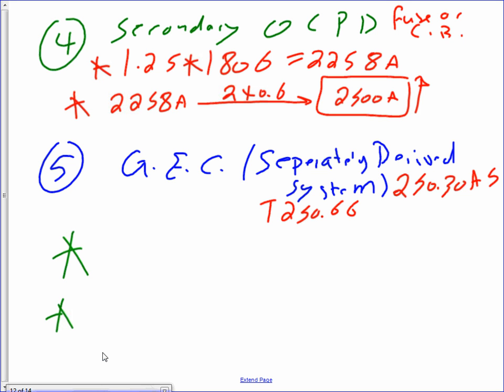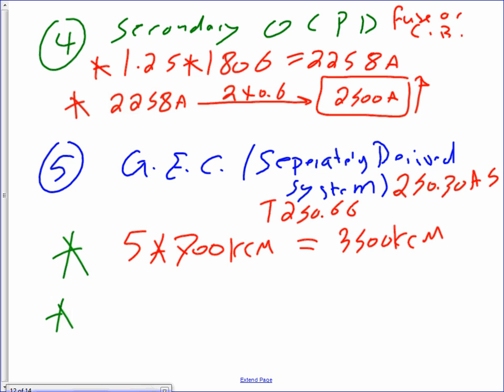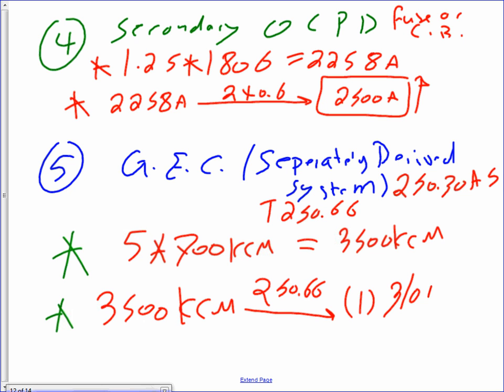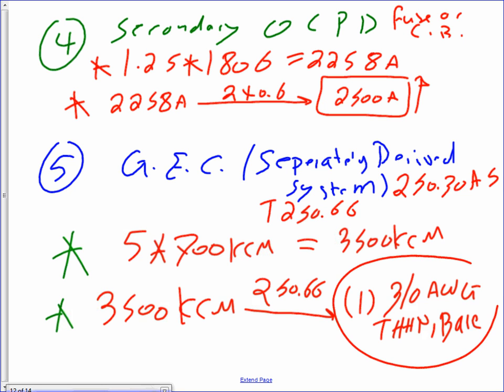Okay, separately derived system, guys, 250.66, 250.30. These are the grounding electrode conductor. Let's go size that baby. For the grounding electrode conductor, guys, I have 5 sets. You multiply them by 700 kcm, and that'll get you 3500 kcm. You take the 3500 kcm to 250.66. That will get you a healthy one conductor, 3/0 AWG THHN, THHW, or bare conductor. This is a grounding electrode conductor. This one will actually take the ground bar and tie it to the ground rod.